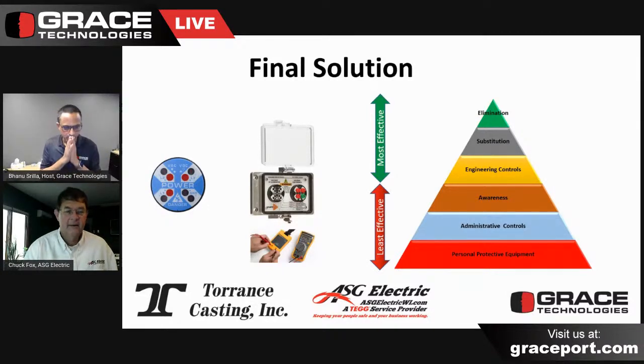Right. Another advantage of the voltage indicator is that it displays what I refer to as an always-on available voltage reading. So if they lose an entire phase for some reason, they could see that condition right off the voltage indicator on the display of the control cabinet with this installed.